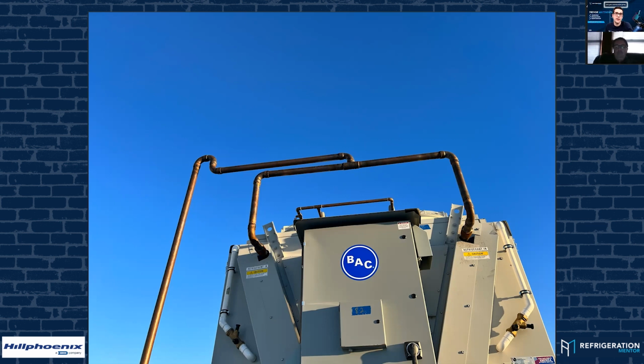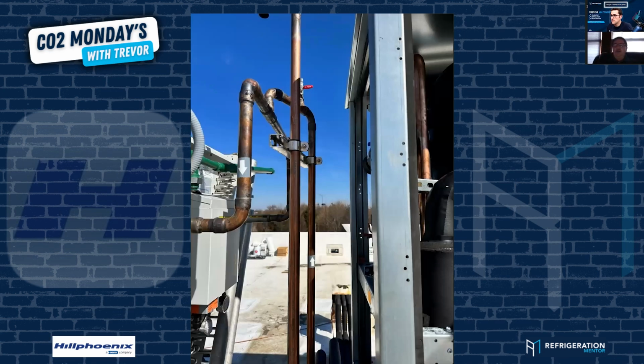You don't do it this way, you don't blow it off, for HFC. You've got to recover that gas off the top. Yep. Just don't blow that out into the atmosphere, guys. You recover it to an empty bottle. Yep, exactly. As you can see here to the left, this is factory piped, and we have a high vent right up here. Yep.